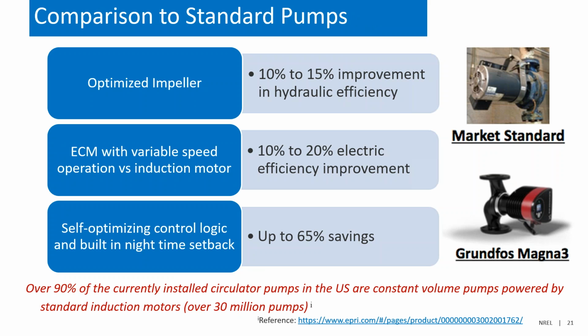So just a quick comparison to other pumps, you'll see these high performance circulator pumps have about a 10 to 15% improvement in hydraulic efficiency. So the pumps themselves are more efficient than other circulator pumps. There's a 10 to 20% improvement in the electric efficiency from the ECM motor. And then really the large savings comes from the ability to ramp the motor up and down to meet the load rather than running it at a constant speed. The one that we looked at does have an integrated nighttime setback that can be programmed in there, but really the large savings comes from that variable speed operation.